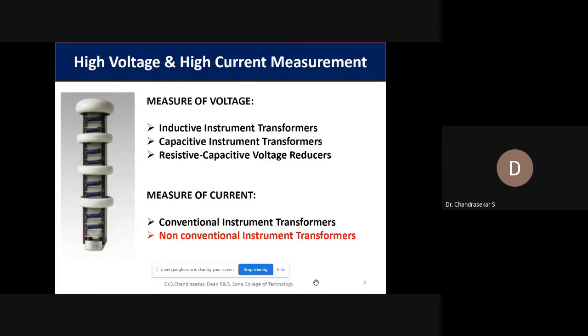In the case of a transformer, you know there is one primary winding and one secondary winding. In between the windings we also use pressboard insulation, a paper or solid insulation. So even inside the transformer, we have both solid insulation and liquid insulation. A hybrid insulation system is followed in such big instruments.